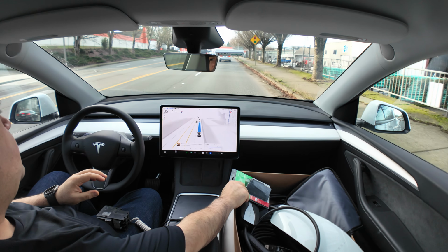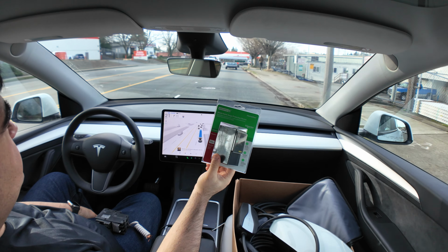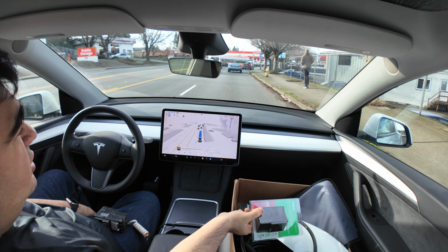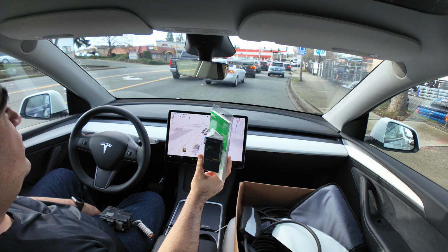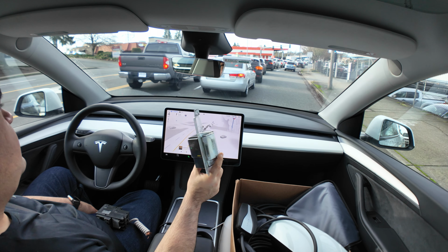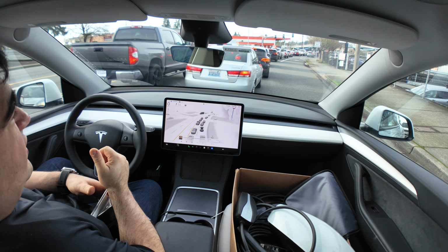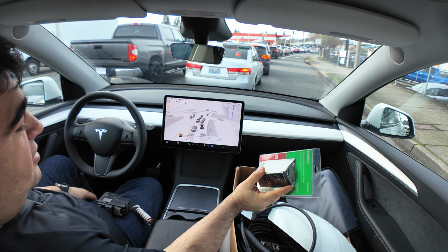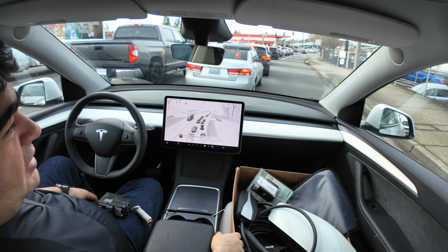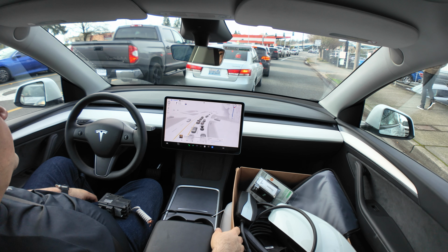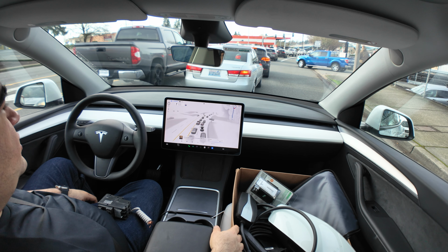The other thing we recommend while installing car charging or anything heavy like this onto your house is an in-home surge protector at your panel. Now, this protects the charger, the car, and everything that's in your house. Typically, people are purchasing power strip style surge protectors for your TV because, well, it's expensive, or your computer. Now you have a $45,000 to $100,000 car plugged into your grid. So, highly recommend you look into additional forms of whole home surge protection to protect everything from a power surge.